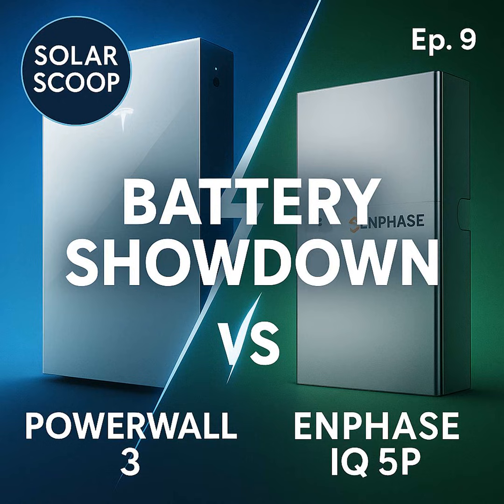A big part of the Powerwall 3 is that it's not just a battery, it has the inverter built in. It's got an integrated hybrid inverter, think of it as the brain managing solar and battery power. And it has 6 MPPTs, maximum power point trackers, which helps squeeze more power out of the solar panels, especially if you have panels facing different directions or partial shading, optimizing the harvest. Plus, that inverter can handle a big solar array, up to 20 kilowatts of solar input, great if you're putting in a new large solar system with a battery.